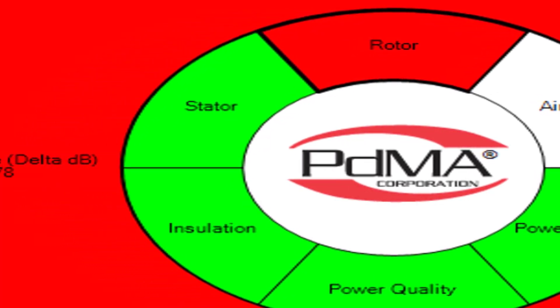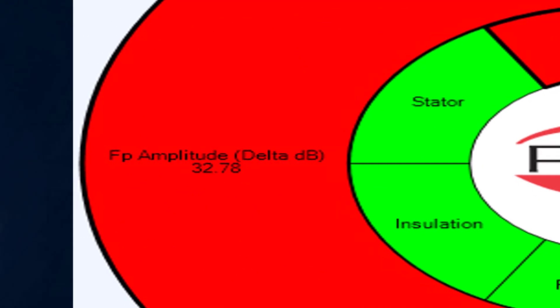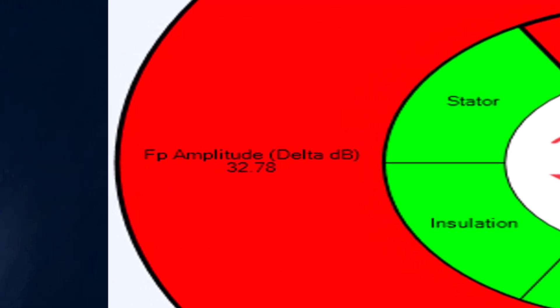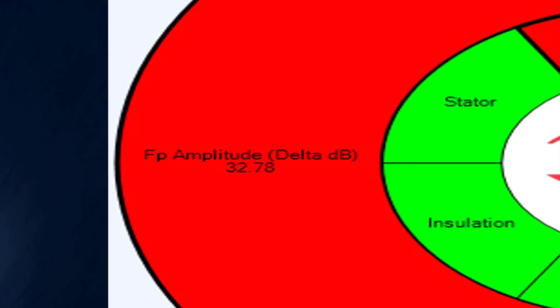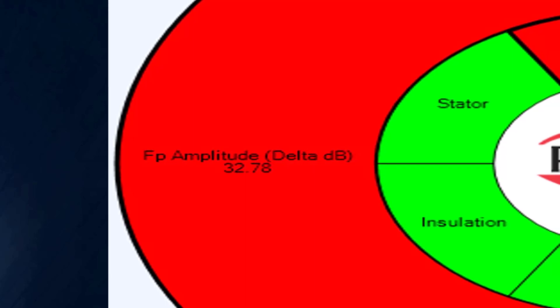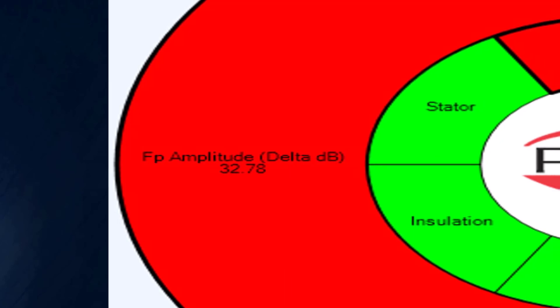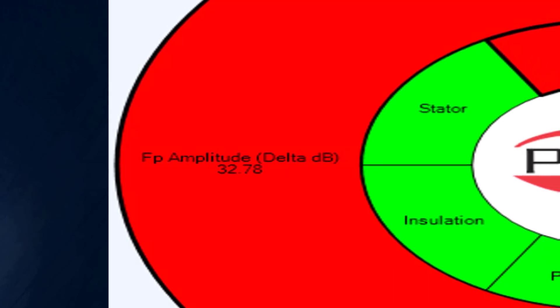Good question. PDMA has collected over the many years of motor testing industry standards from everyone — from IEEE, ESA, NEMA, EPRI studies — we've built all those standards into our caution and alarm set points, including PDMA standards that we ourselves have developed over the many years of analysis. Even though we're showing the rotor, which is in red, and the outer ring shows the actual set point for it, you could do the same for stator, insulation, power quality, power circuit, air gap — they all have numbers.